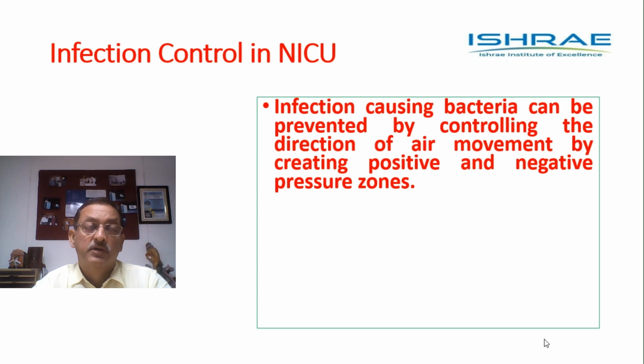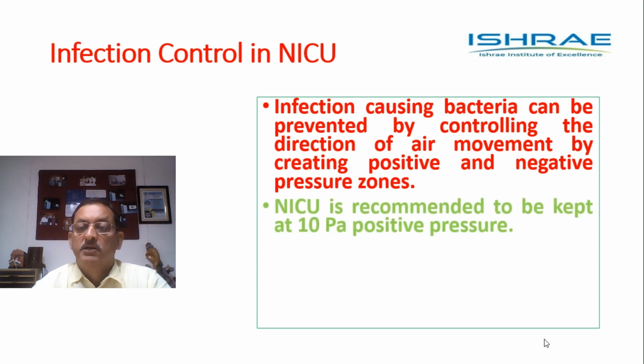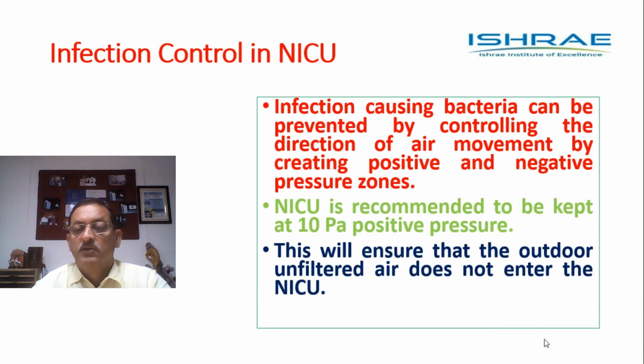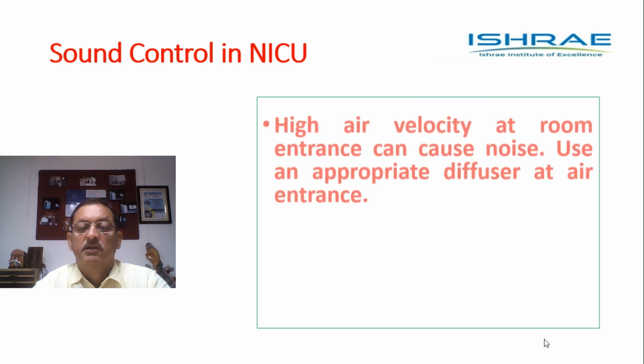Infection control in NICU. How do we control the spread of infections? We are injecting fresh air inside the NICU, but how do we ensure that only fresh air comes in contact with the infants? That can be done by controlling the pressurization in the compartment. Typically, a NICU should be kept at slight positive pressure so that the air movement always takes place from positive to negative, and unfiltered air from outside will not come in contact with the infants. Infection causing bacteria can be prevented by controlling the direction of air movement by creating positive and negative pressure zones. NICU is recommended to be kept at 10 Pascal positive pressure, and this will ensure that the outdoor unfiltered air does not enter the NICU.